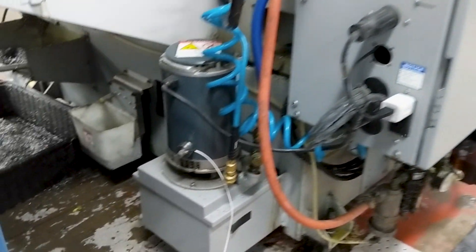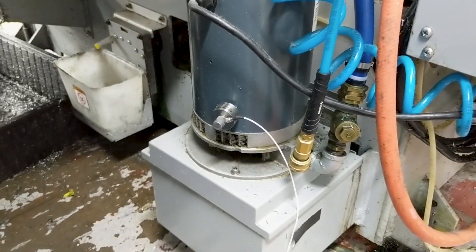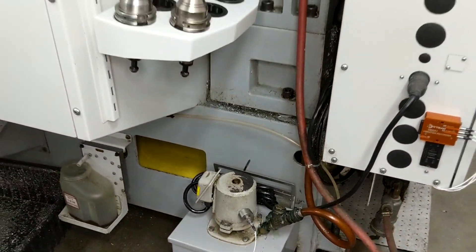We found that the coolant pump, which operates throughout the entire duration of a CNC job, provides consistent vibration levels that can be used to determine clear on and off states for each machine.